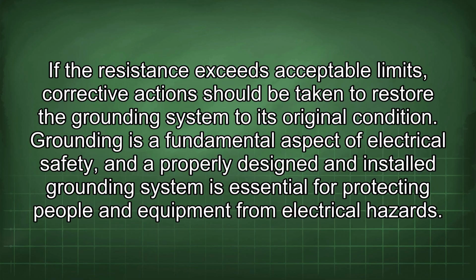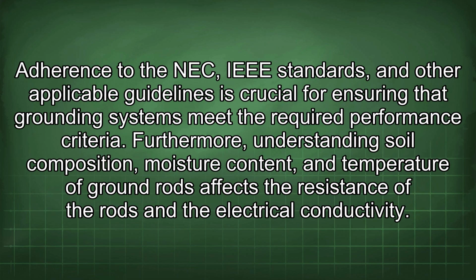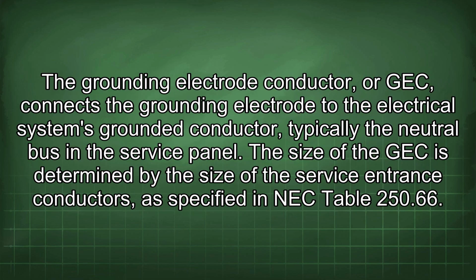Grounding is a fundamental aspect of electrical safety, and a properly designed and installed grounding system is essential for protecting people and equipment from electrical hazards. Adherence to the NEC, IEEE standards, and other applicable guidelines is crucial for ensuring that grounding systems meet the required performance criteria. Furthermore, understanding soil composition, moisture content, and temperature of ground rods affects the resistance of the rods and the electrical conductivity. The grounding electrode conductor, or GEC, connects the grounding electrode to the electrical system's grounded conductor, typically the neutral bus in the service panel.